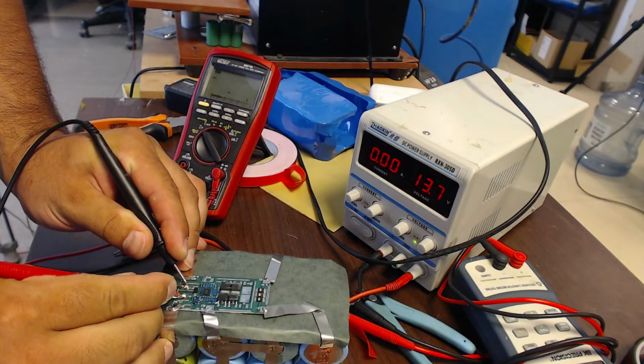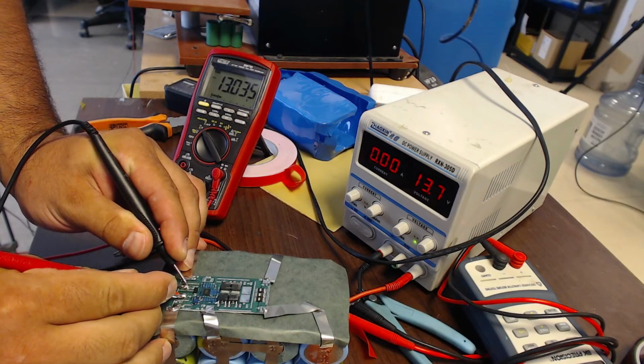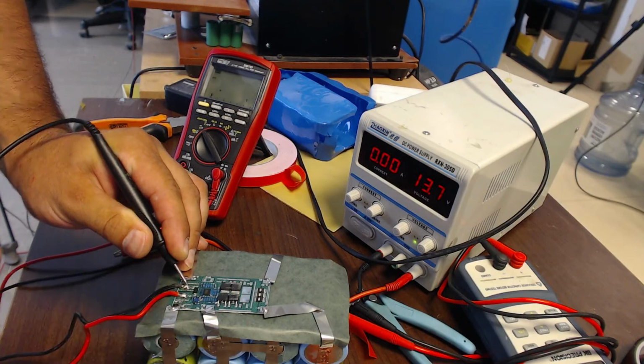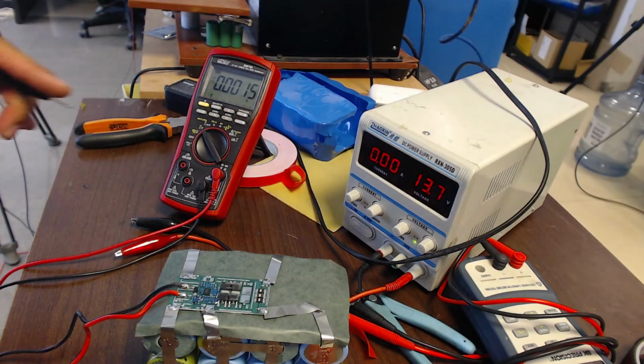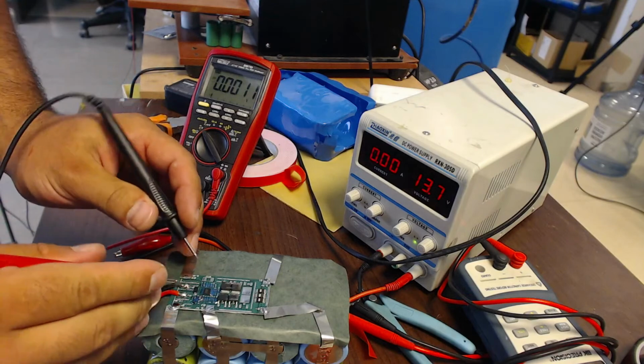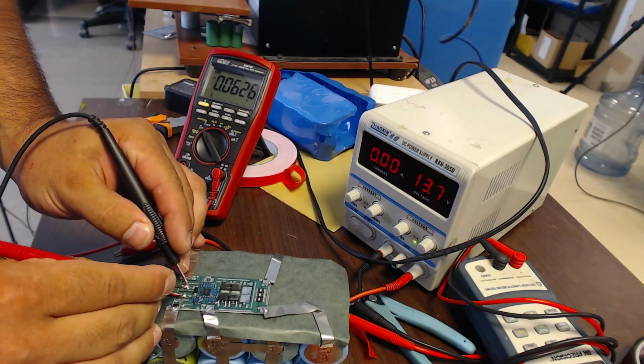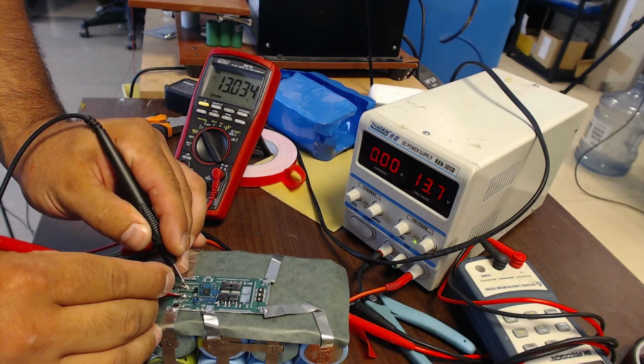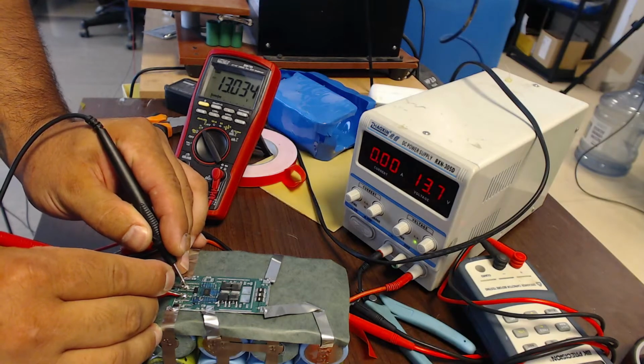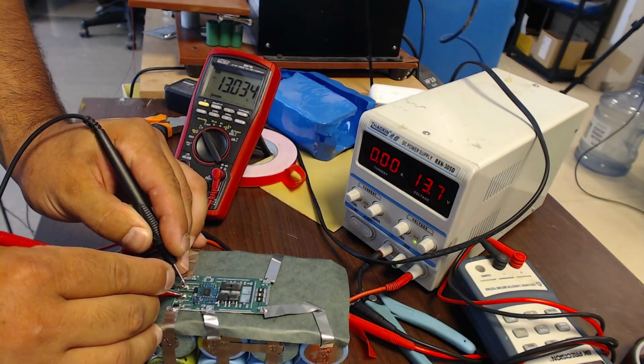And you can see that the BMS opened. It was closed because when you remove the cells, it will get into a protection mode. It detects that that cell is under voltage, gets into protection, and it will reset usually when you're applying power to it.